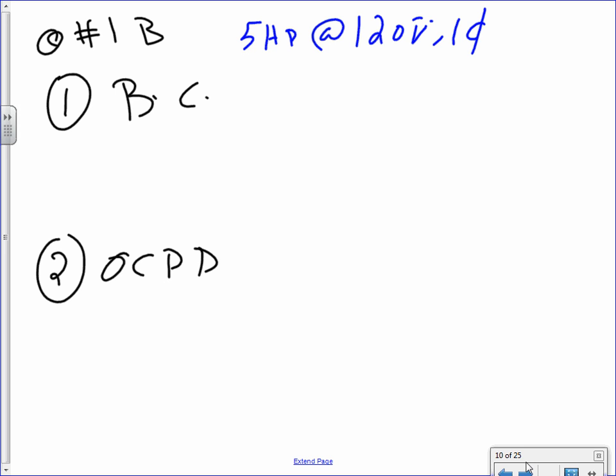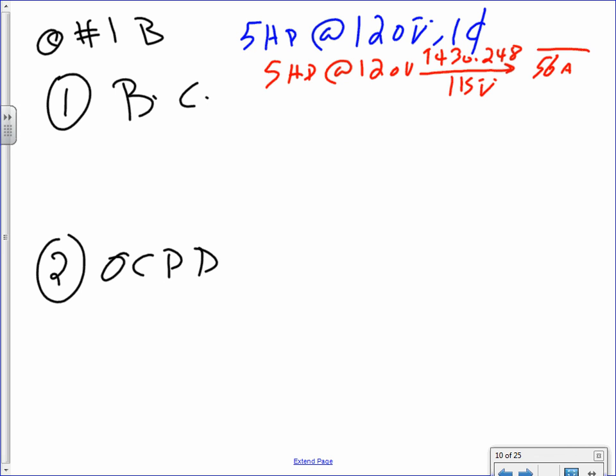120. So first, if you take 5 horsepower at 120 volt, take it to table 430.248 under 115 volt, you get yourself a healthy 56 amps. Everybody knows where the 56 amps came to be? That's basically from the full load current of that equipment.